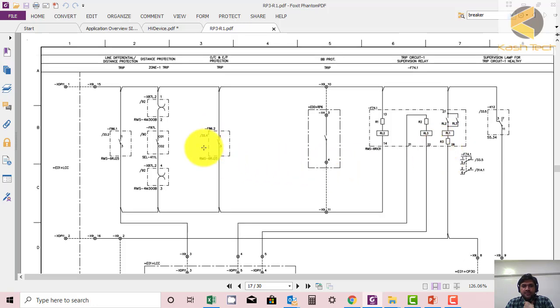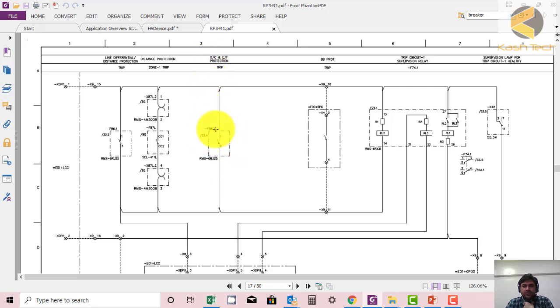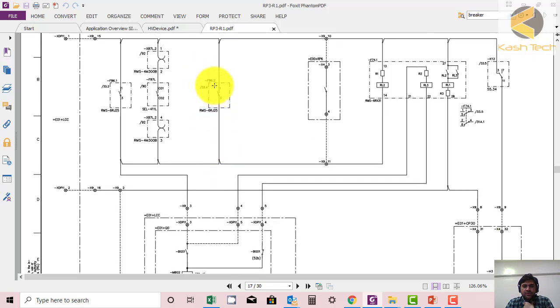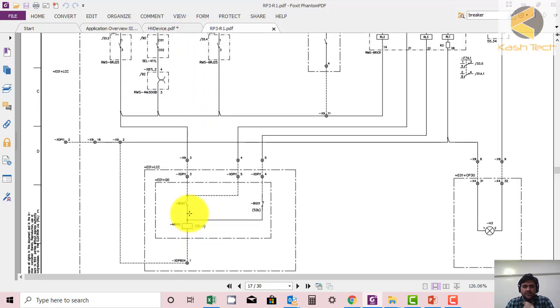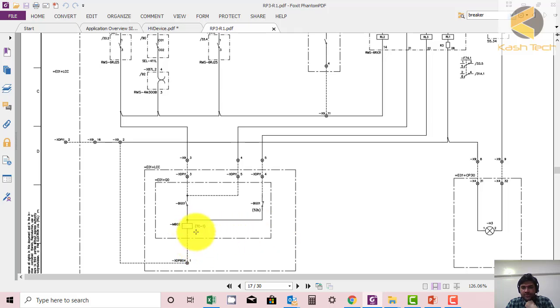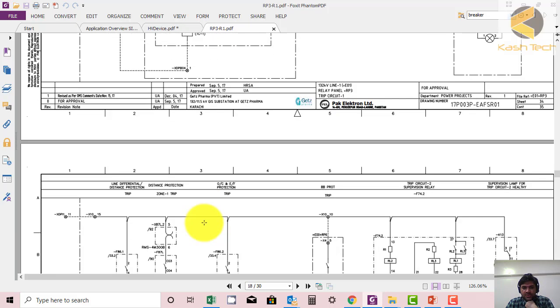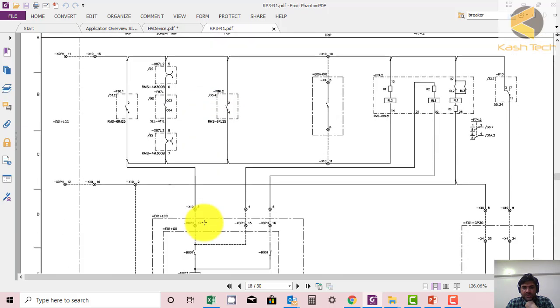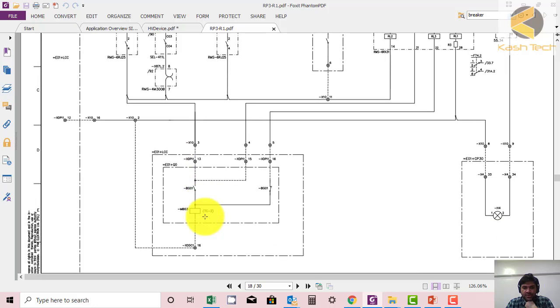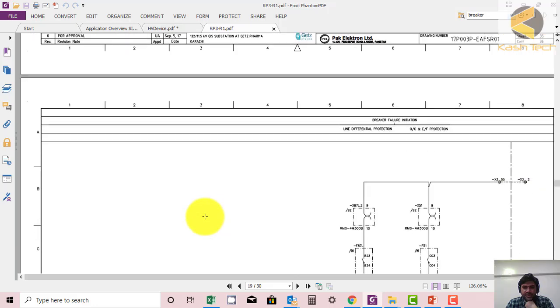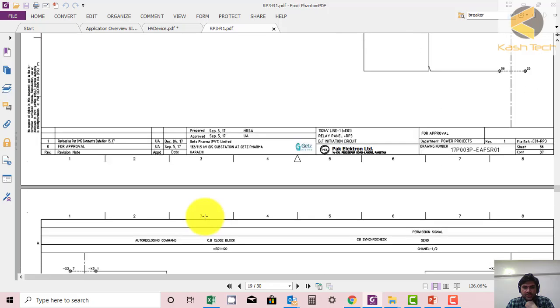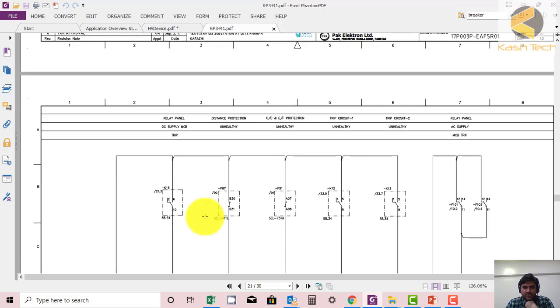The tripping is coming from a protection relay. The protection relay is operating lockout relay F86.2, and then lockout relay F86.2 is giving tripping. This contact will close - it's available here. Then it will come here, and through this auxiliary contact of the breaker 52A and B, it will trip. This is just a simple explanation. Even if you're not understanding, don't worry. I will explain this all in detail in the coming lectures.